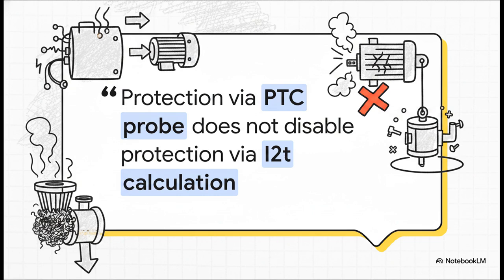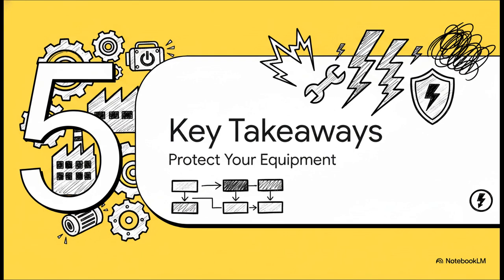This real-life scenario perfectly highlights why we absolutely cannot rely on factory defaults. Think about it. If the drive had just been left at its factory default rating, it would have happily pumped maximum current into that struggling motor until the internal windings completely failed. A simple clogged filter would have turned into pulling a massive pump out of the ground, a hugely expensive and time-consuming disaster.